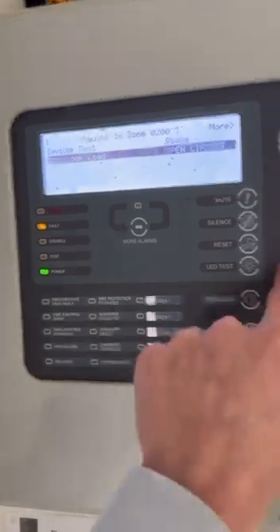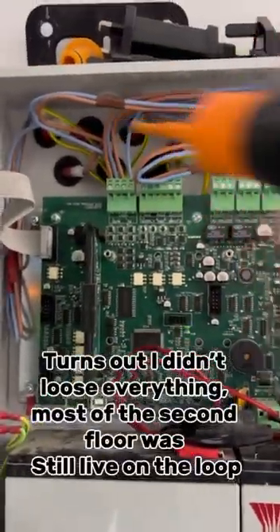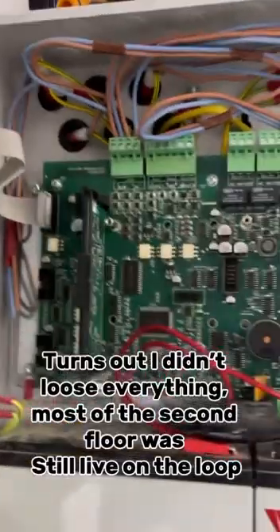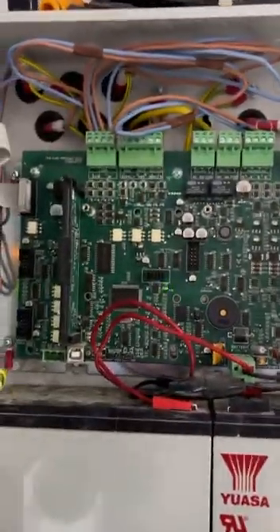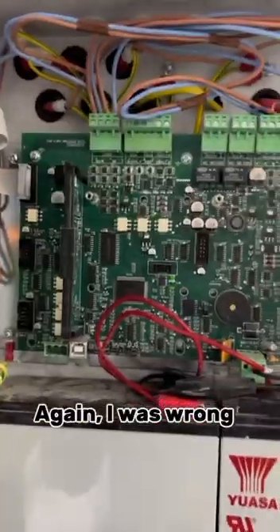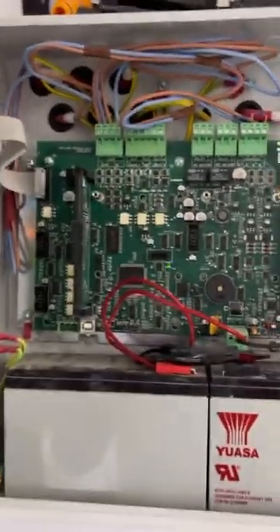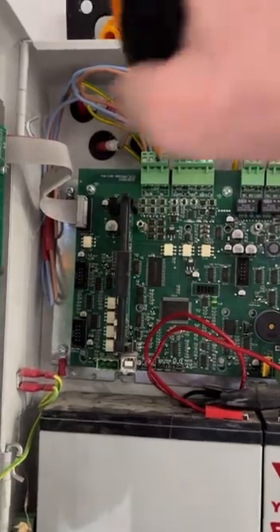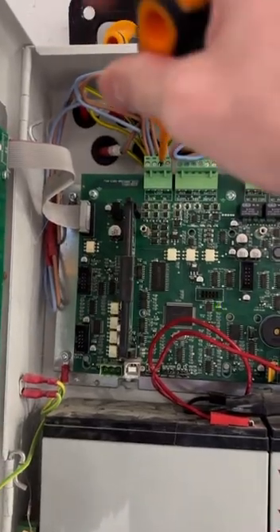We've got a loop open circuit. I disconnected one leg of the loop and I lost everything, so I assume it's somewhere close to the panel. I'm going to disconnect the other loop and see what we get from that.